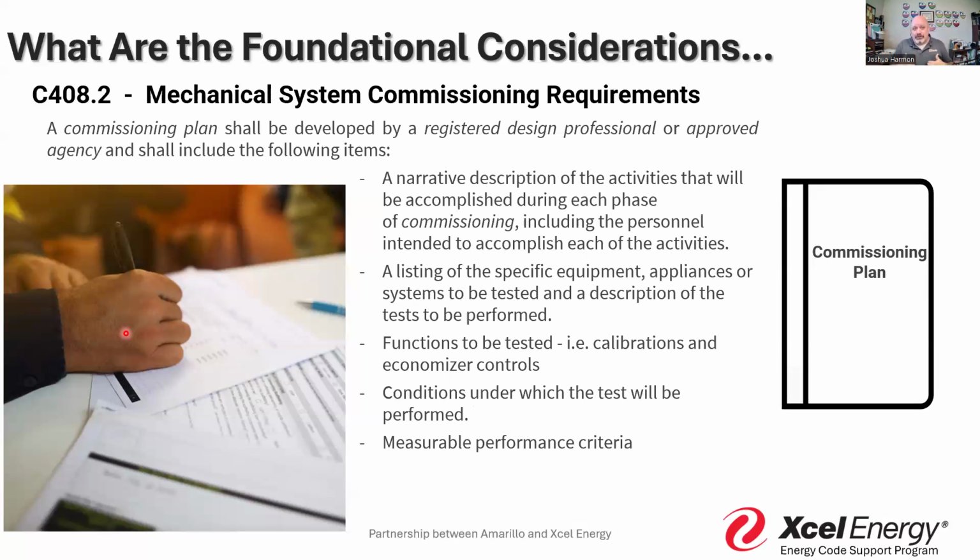Now remember, I'm looking at a design with some specific things I'm looking for. I'm looking for the right jurisdiction, the right elevation, the right components in that design. I'm not rerunning the design. I'm just saying you have a design, and you've selected equipment that matches that capacity. So I have a load, a capacity, they match. I'm good. That's the end. I am not redesigning their system.